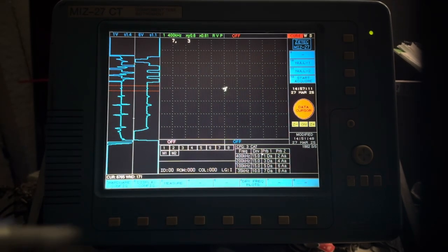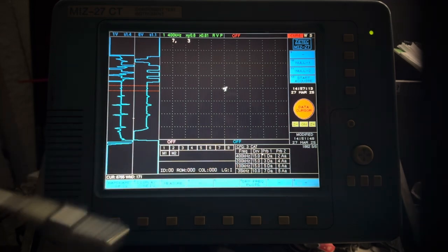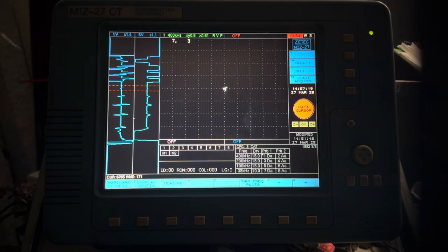So to demonstrate this, I have an Inconel tube. I'm going to be using an inside bobbin probe. And this tube's got a drilled support plate on one end. It's got a broached support plate on the other. And it's got a 100% through-wall hole, 80% flat bottom hole from the OD, 60% flat bottom hole, 40, 20 flat bottom hole from the OD.